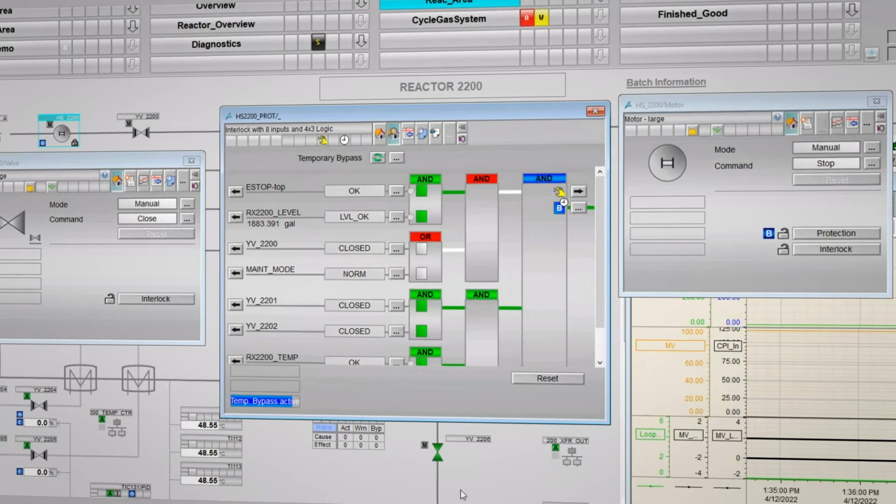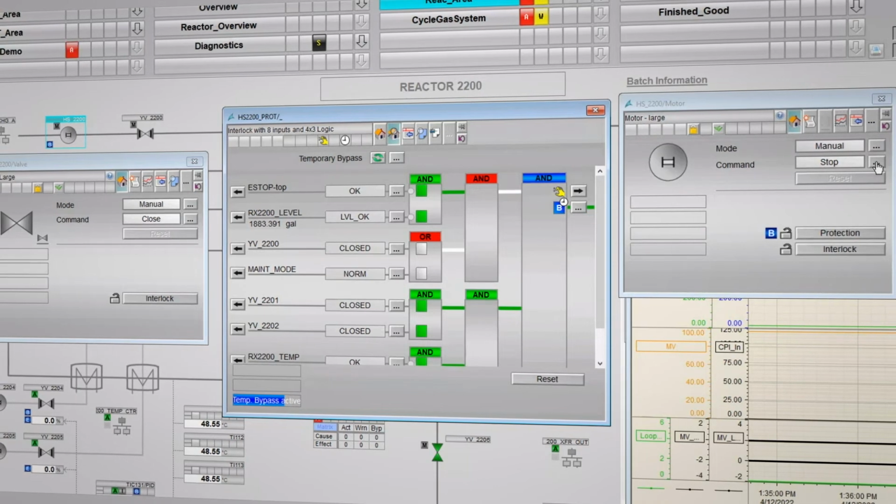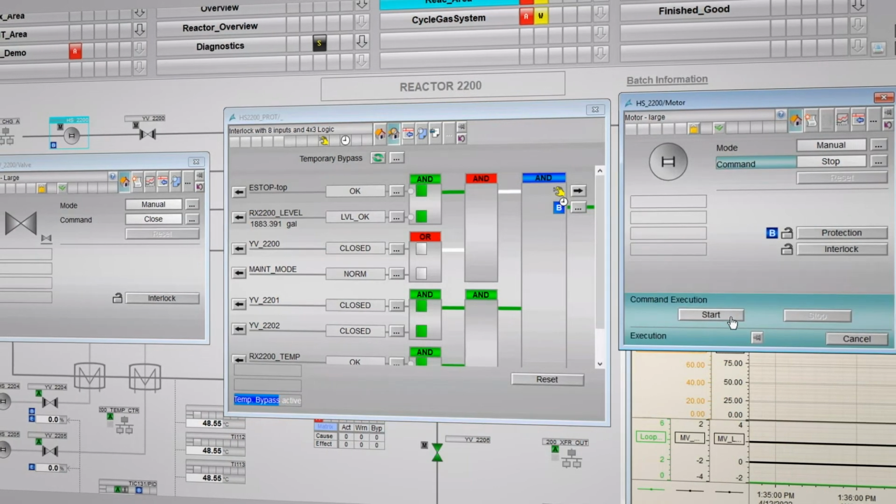At times like these, we may want to bypass the entire condition. The 4x3 offers both permanent and temporary bypass functions. Engineered times are configured for temporary bypassing, for example, 10 minutes or an entire shift.